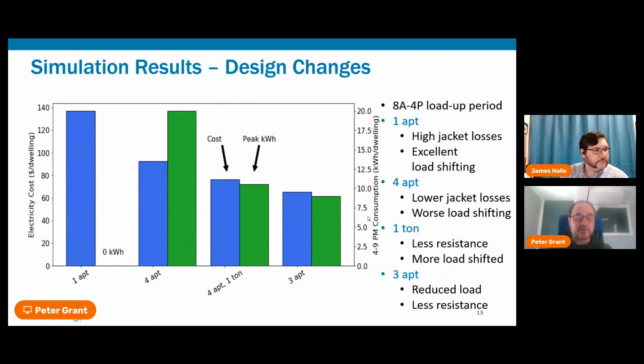And this, of course, is because it's shared. Now you have 20 gallons of storage per apartment instead of 50, and you have 1/4 as much heating power per apartment. So the heat pump water heater simply can't perform as well during the load up period, and it simply has less storage per apartment to coast through the peak period. And then, as I'm sure will surprise nobody, when we use that same shared configuration with a 1-ton compressor, you have lower electricity cost and lower peak period electricity consumption. And this is just because the bigger compressor can keep up with the load better. It doesn't have to use the electric resistance elements as much, and it does a better job of loading up before the peak period. And we're running a little bit late, so I'll skip over the 3 apartment case, but you can see there were savings there as well.